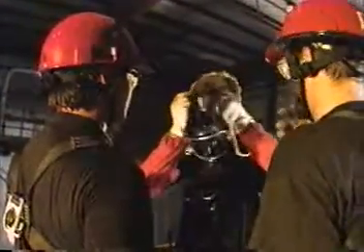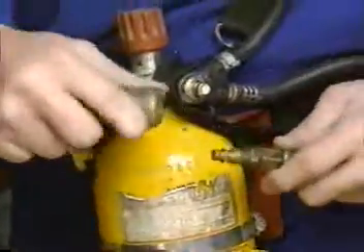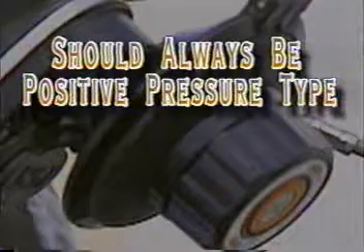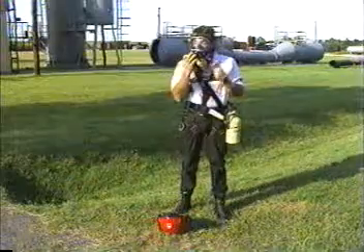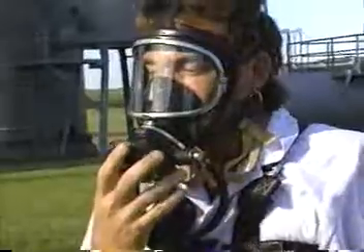Simply speaking, there are 3 types of respiratory protection recommended for hydrogen sulfide environments: escape packs, airline units, and self-contained breathing apparatus, or SCBA, rated for 15, 30, 45, or 60 minutes. Remember, your breathing apparatus should always be positive pressure type. Never use air purifying or cartridge type in hydrogen sulfide environments. Positive pressure type provides a slight positive pressure inside the facepiece, preventing contamination from entering even if leaks occur.